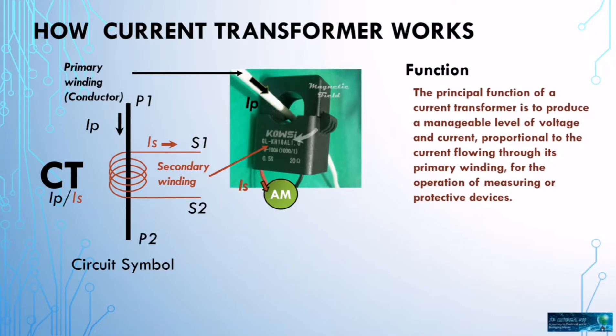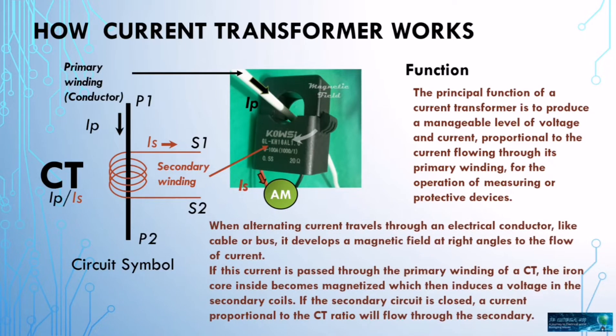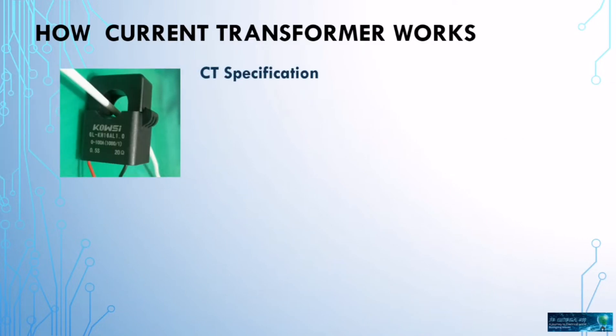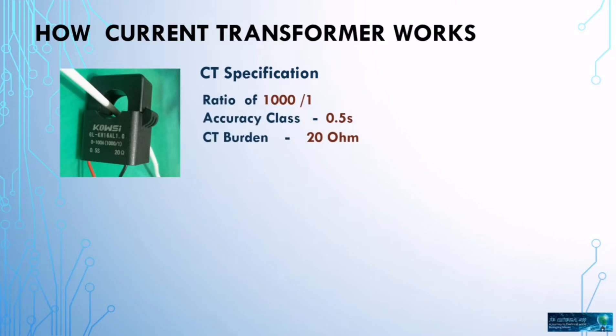When alternating current travels through an electrical conductor like a cable or bus, it develops a magnetic field at right angle to the flow of current. If this current is passed through the primary winding of a CT, the iron core inside becomes magnetized, which then induces a voltage in the secondary coil. If the secondary circuit is closed, a current proportional to the CT ratio will flow through the secondary winding.